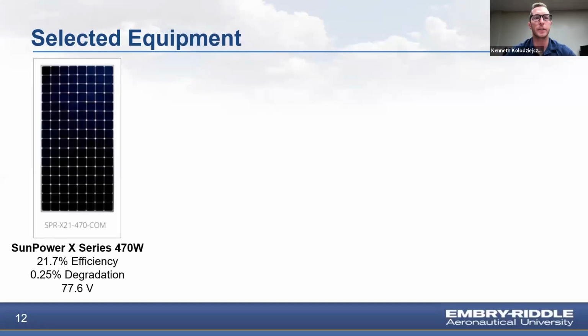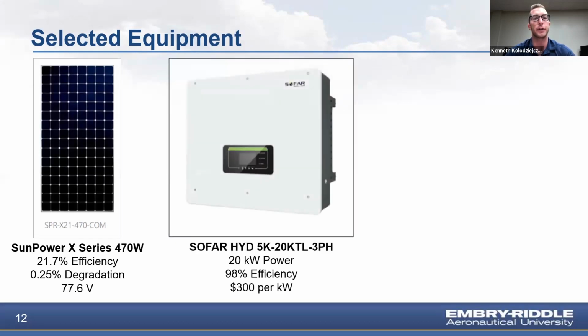The selected panel is the SunPower X Series 470 watt. This panel had the highest efficiency, lowest degradation rate, and optimal voltage compared to all the panels considered. The selected inverter is the SOFAR HYD. We chose a hybrid inverter over a string inverter paired with a battery charge controller to simplify the interconnection process. A hybrid inverter has the ability to charge and discharge batteries, which means less components are needed. The SOFAR HYD is also a UL 1741 approved inverter and has anti-islanding capabilities in the event of a power outage.